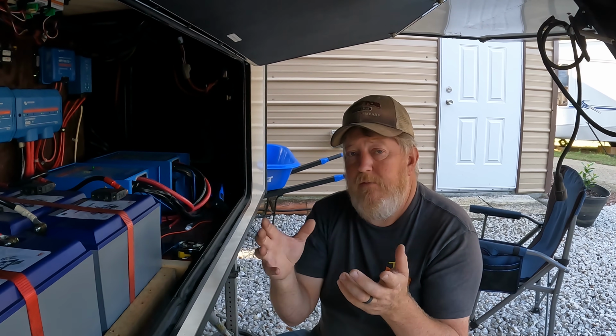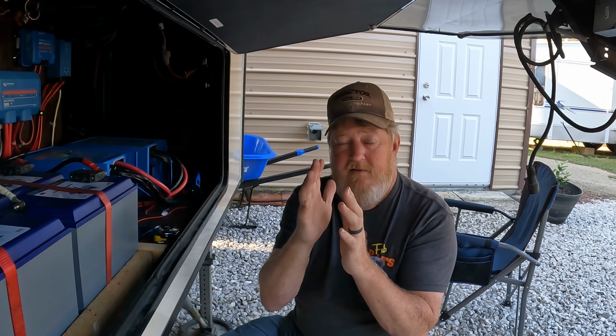Some of the videos Will did were pretty impressive, showing the damage from other people running these. They don't think it's going to burn your camper down, they say it's going to open the circuit. But if you look at it, there's a plate, a bus bar, and a bolt through it. By melting the plastic out of the middle, all you've done is create a high resistance connection, which creates heat. It doesn't open like a thermal fuse or a circuit breaker would.